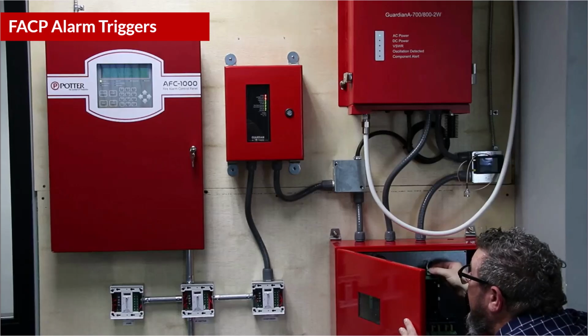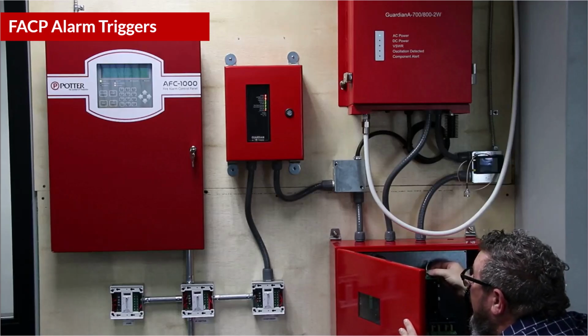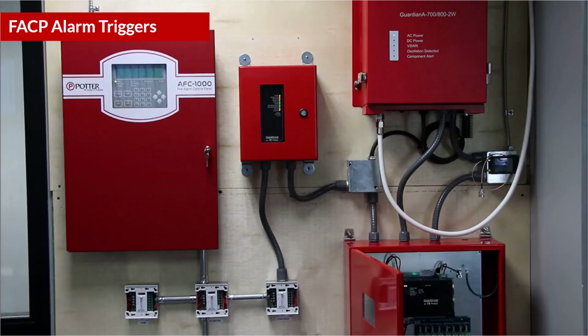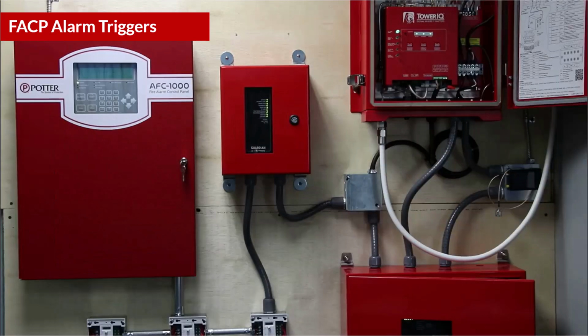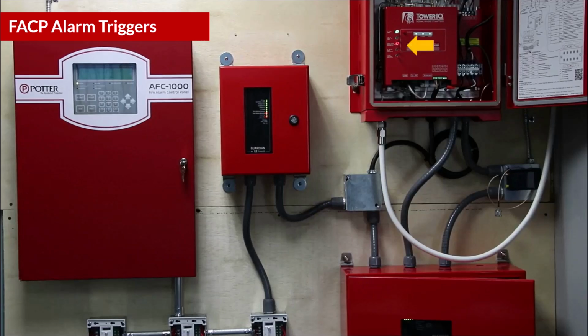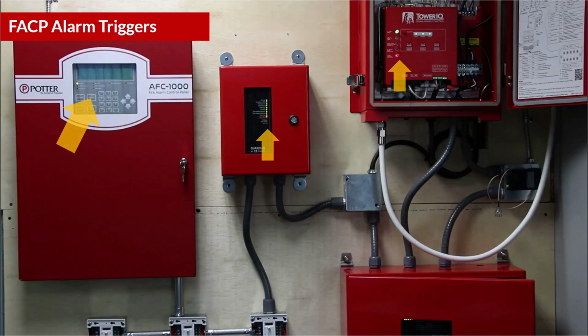If connected to the FACP, your alarms should show up as supervisory alerts when activated. As you activate each individual alarm, they should also activate on the FACP. If they do not, ensure the wiring has been done properly per the manufacturer's instructions.